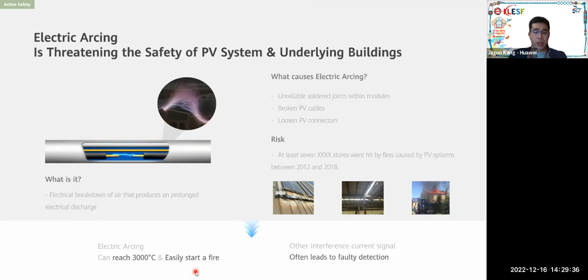So what actually causes this DC arc, as you can see here, is pretty common. If there are unreliable joints within the PV module, this is a manufacturing defect from the PV module junction box, it will cause a DC arc. Then if there's a broken PV cable, this is pretty common as well, and loose PV connectors, as we know that when PV modules are installed on top of the roof, there's vibration on top of the roof. So as it ages, all these problems will then exist, and you'll have this electrical arcing issue, whereby an electrical arc will happen and start a fire easily, as you can see in the picture over here.